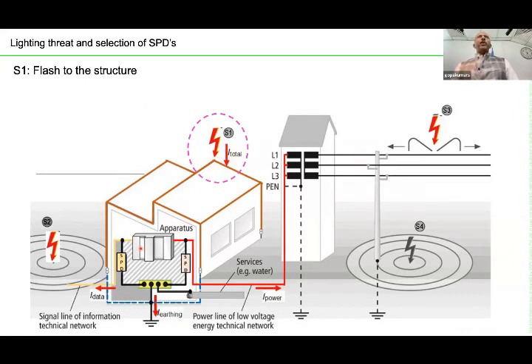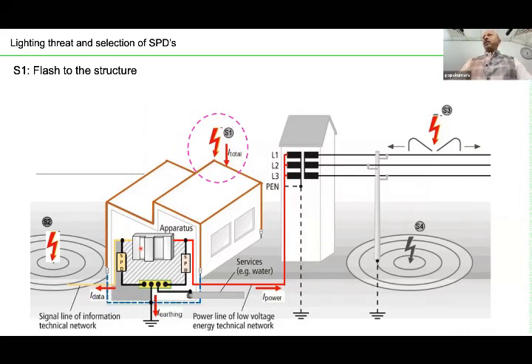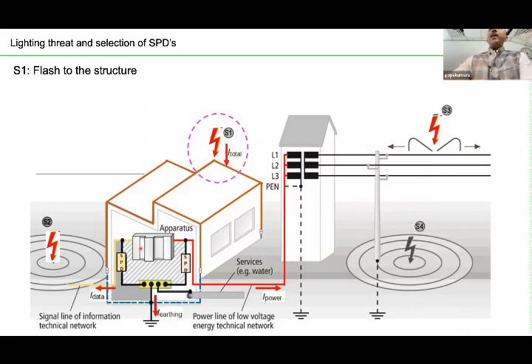When we talk about an external lightning protection system, please note that most of the buildings in Sri Lanka have a single down conductor lightning rod. That means one rod at the top and only one down conductor, which is very dangerous. The standard never recommends going for one down conductor. You need to have multiple down conductors. With one down conductor, if we calculate, you have to take the down conductor maybe 2 meters away from the building. Practically, it won't work.